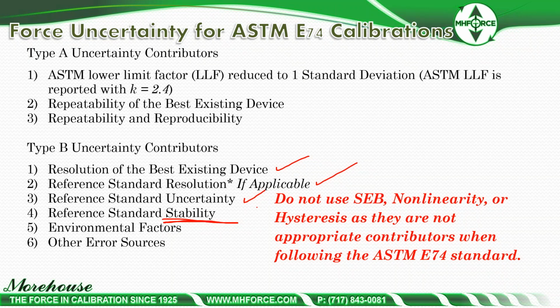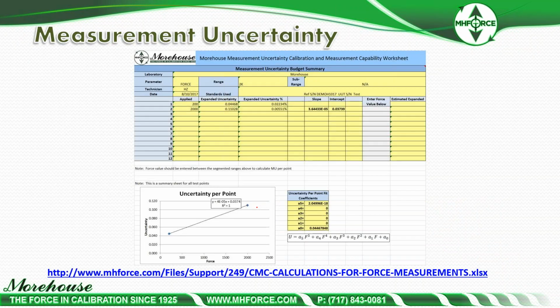We have numerous customers send us in instruments and say, hey, calibrate this to an accuracy of 0.1% of applied. We calibrate the cell. It obviously from the last year has changed more than 0.1%. We adjust it back in. I look at the company scope and they say they can do 0.1%. They're just simply not accounting for reference standard stability, which needs to be accounted for. Environmental factors and other error sources. And reference standard stability can also be type A in there.